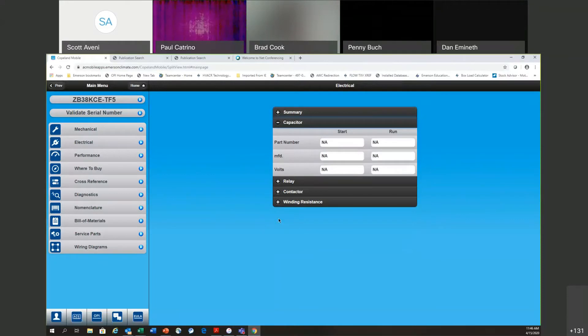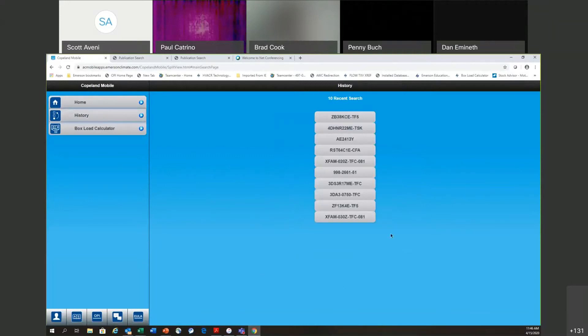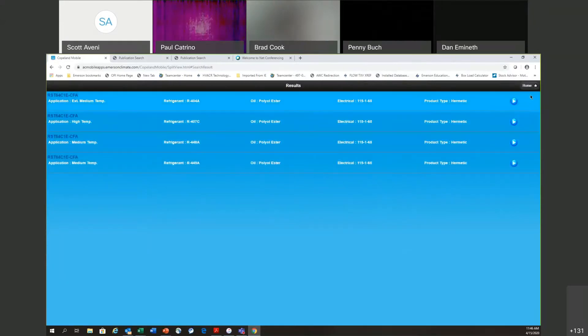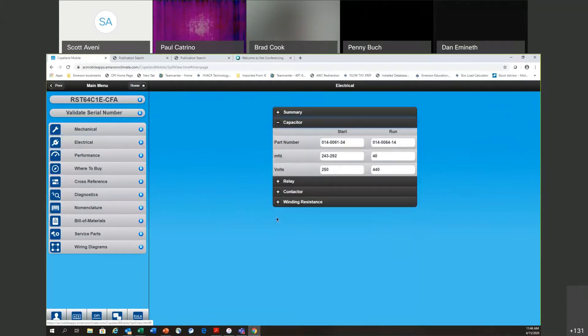Because this is a three-phase model there is no capacitor or relay listed. Let me go back to history and pull up a single-phase compressor. Now on the electrical tab, because it's single-phase, we do have start cap and run cap listed. Here's your start cap with a rating of 243 to 292 MFD at 250 VAC, and the run cap is a 40 at 440. Very fast way to get these capacitor ratings.